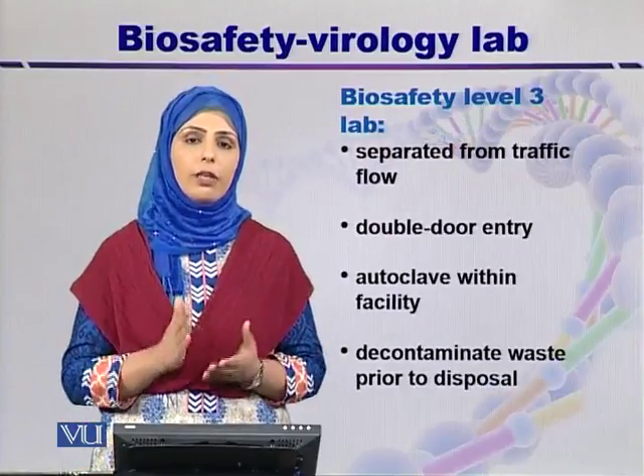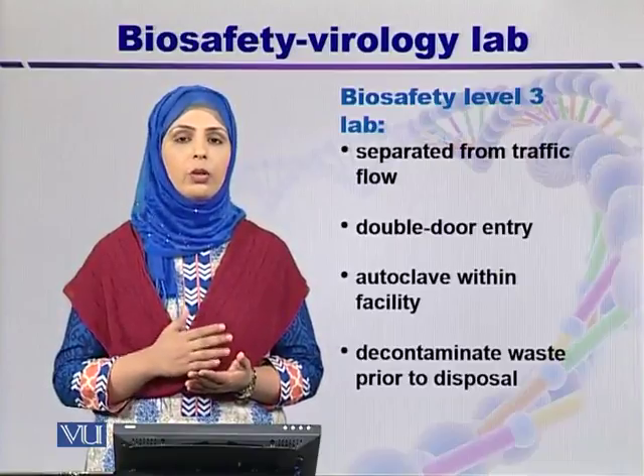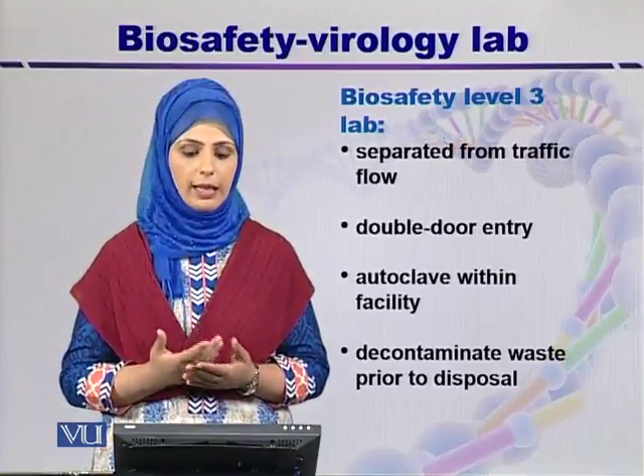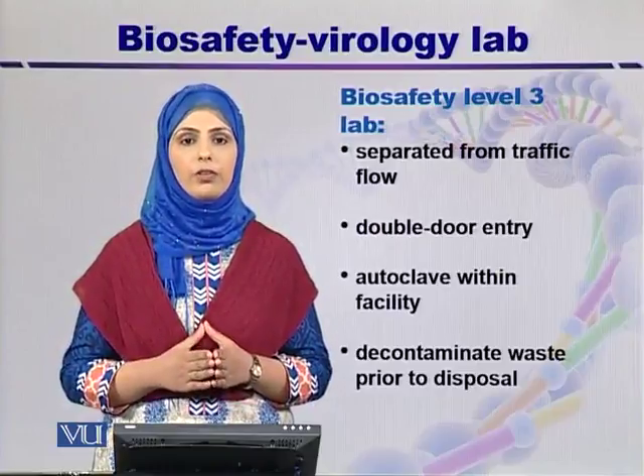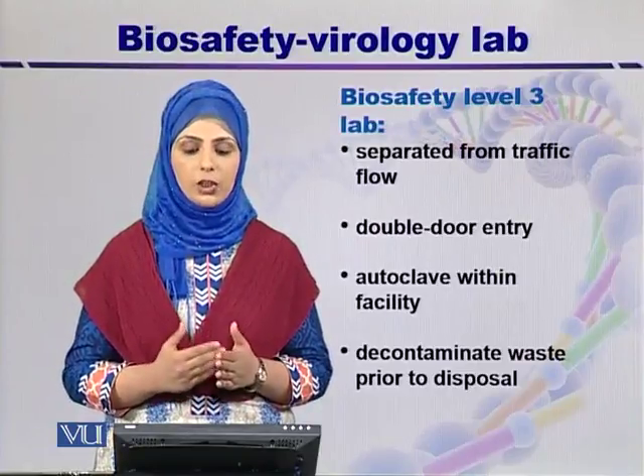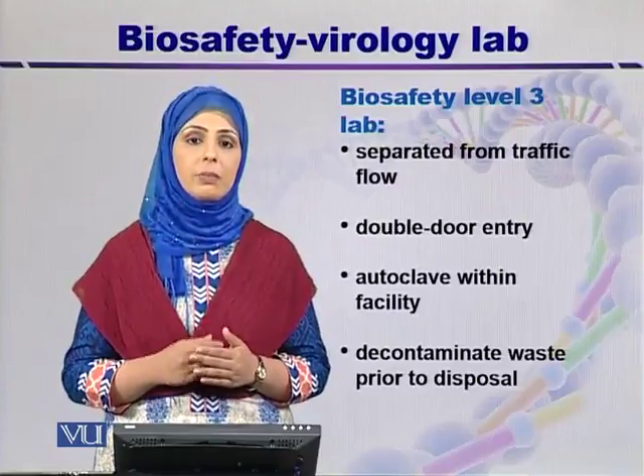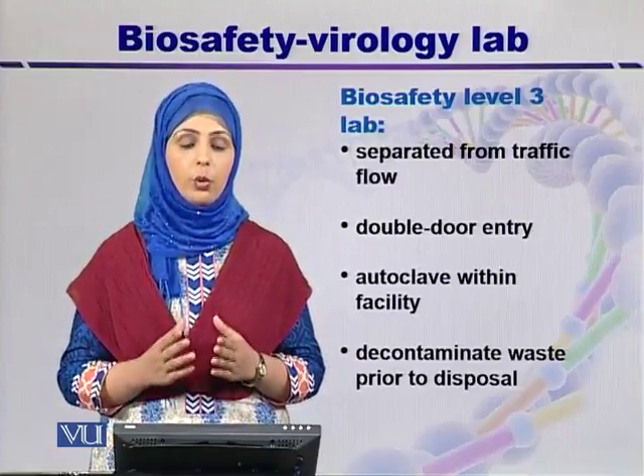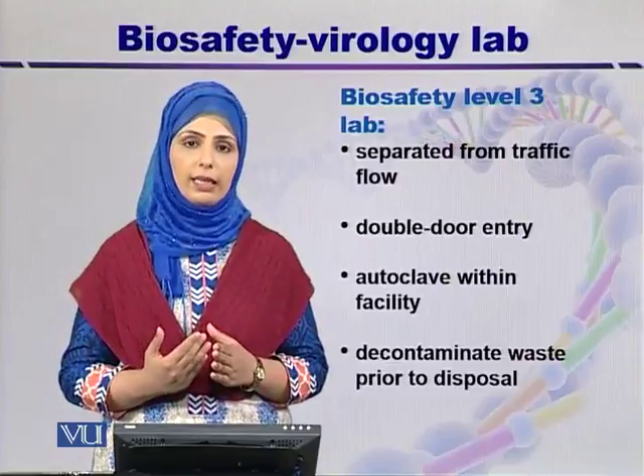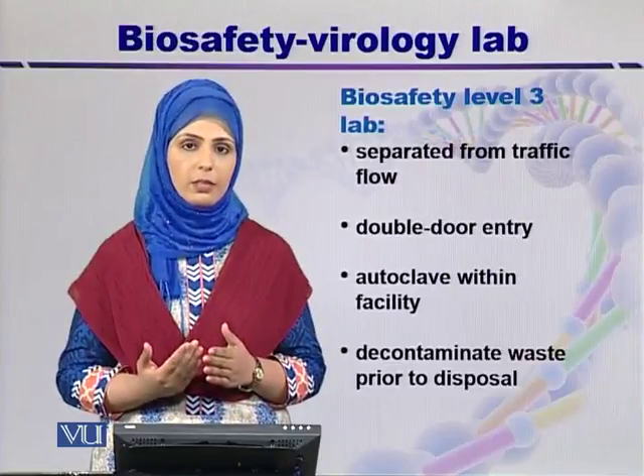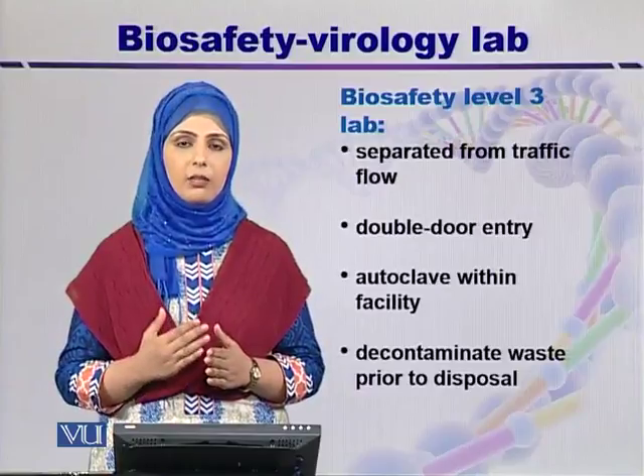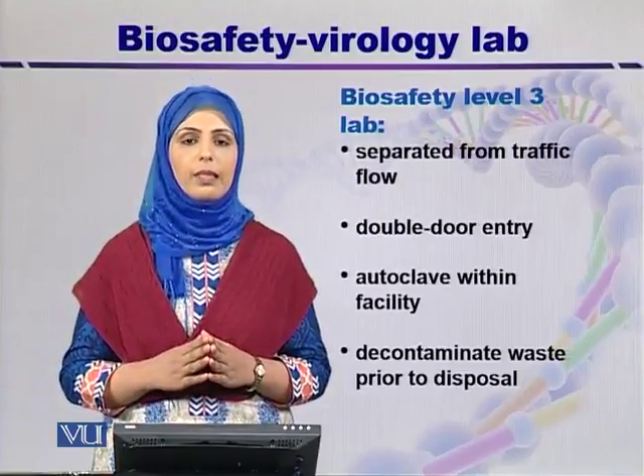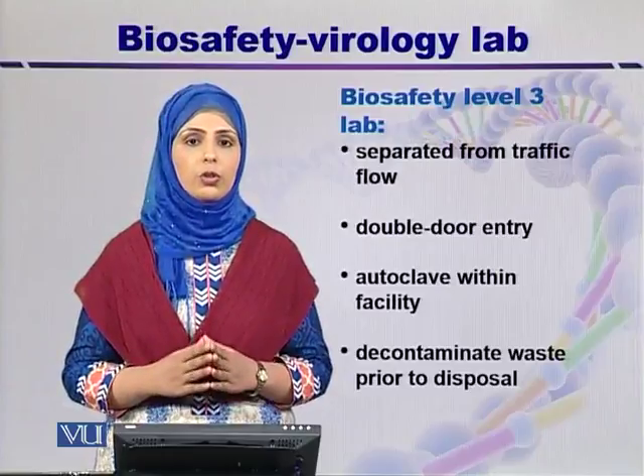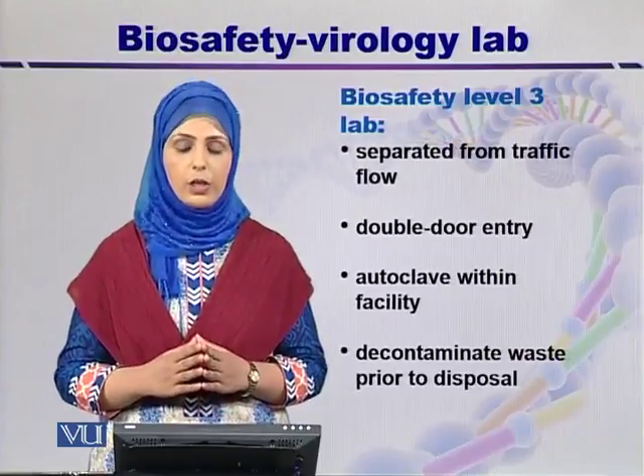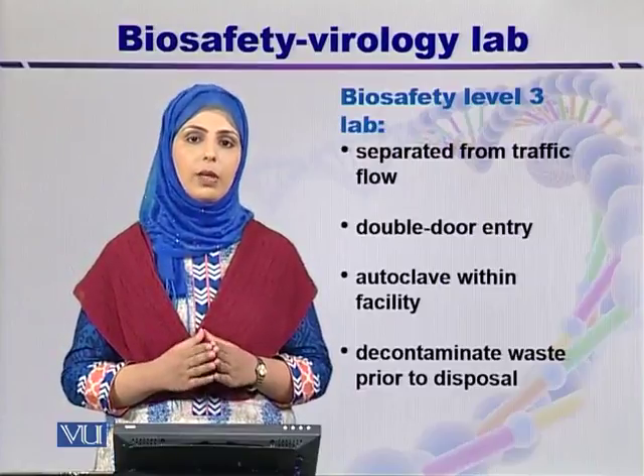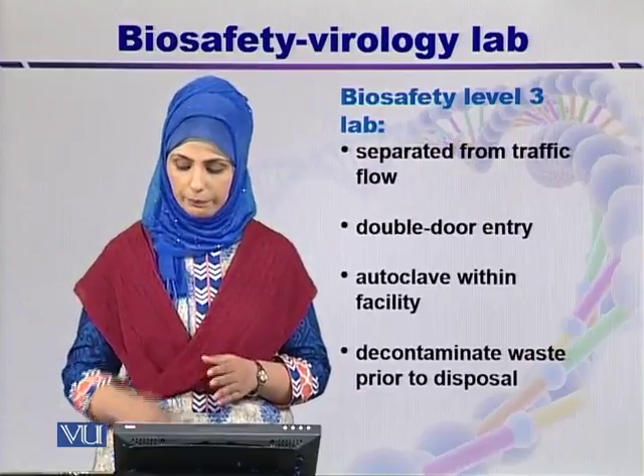Now for every virology lab, we follow a typical biosafety level 3 lab. It should be separate from the traffic flow so that contamination can be prevented. There must be interlocking and double door entry. One door is for entry, that is only for authorized persons, while the exit is from the other side of the door. Similarly, it is better to use an autoclave within the facility so that we can decontaminate the waste prior to its disposal.